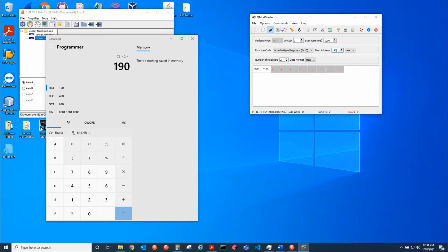because this parameter is assigned to 16-bit registers. So yeah, that went through, and now we will go ahead and do the next parameter, which was the desired state. So 0x24 is the desired state, times 2 is 48, and right now it's 1E. For position program, though, we're going to change that to be 15, hex 15, which is 21 in decimal. And yeah, let's write that.